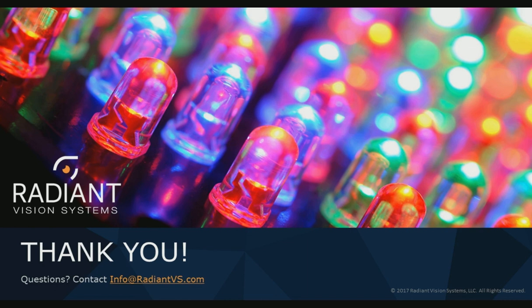If you are trying to build a comprehensive ray set, you can increase the resolution of the scan in order to provide more raw data points, and less interpolation that way. I will say that for a typical scan, we're performing about 1,500 measurements over the forward distribution of a luminaire. And with our latest NFMS software, thanks to some new speed improvements, that only takes a couple hours or less. So that's really great.